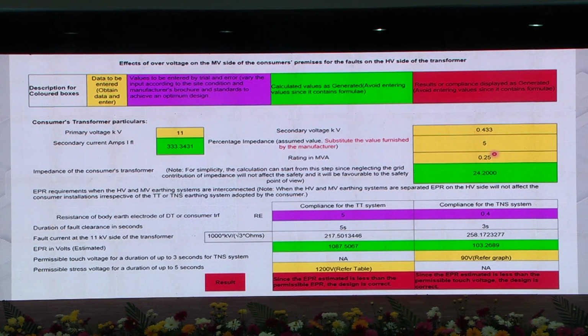Here, for example, for a typical 250 kVA transformer, assuming a 5% impedance and a secondary voltage of 433 volt, the primary is 11 kV and the secondary current is 333. The primary current will be around 13, and the short circuit current based on the percentage impedance will be 20 into 13, around 260. So for this 250 kVA, that 260 will be reduced because of your TT connection and a TNS connection. In case there is a TT connection, a typical value of fault current at the secondary side of the transformer will be 217 for this much of ohms.